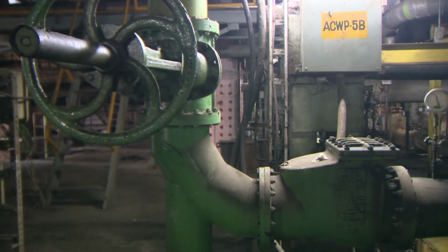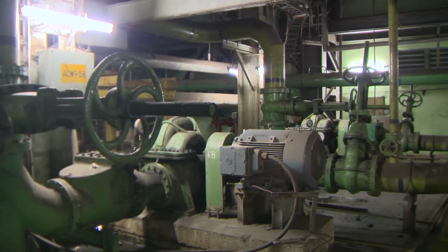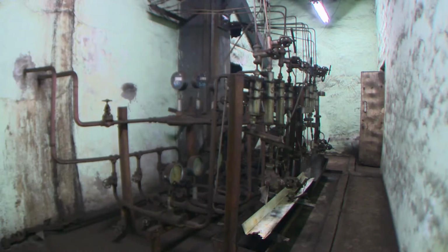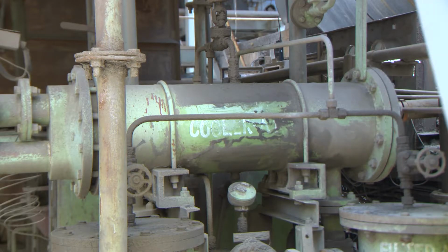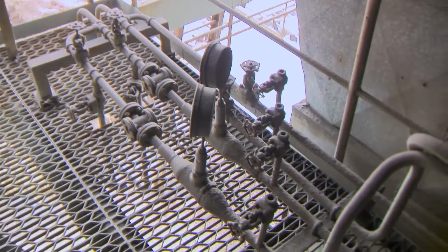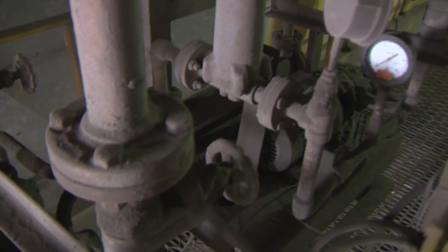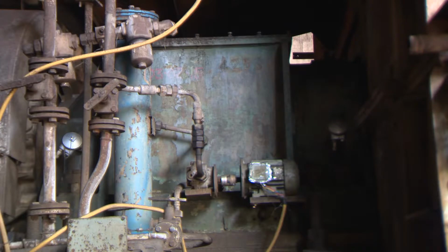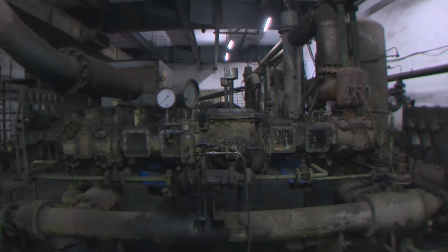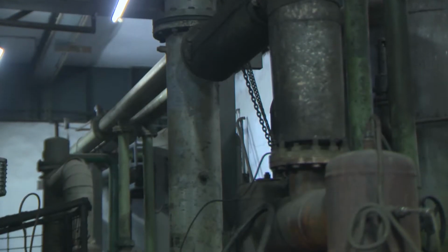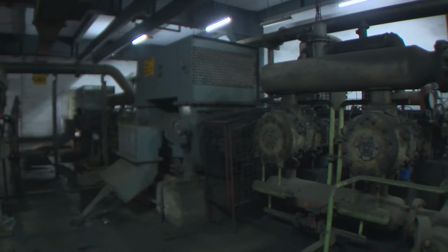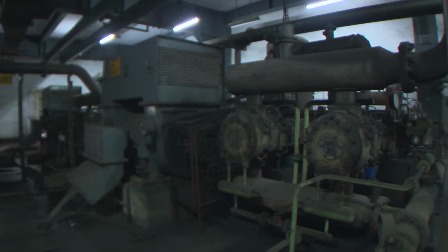Auxiliary cooling water is used in the following auxiliaries. In boiler zone, steam and water analysis sample coolers, lube oil coolers of ID fans, FD fans, air preheaters, pulverizer mills and afterburning grate shaft cooling. In air compressors, intercooler, aftercooler, jacket cooling of HP and LP cylinder.